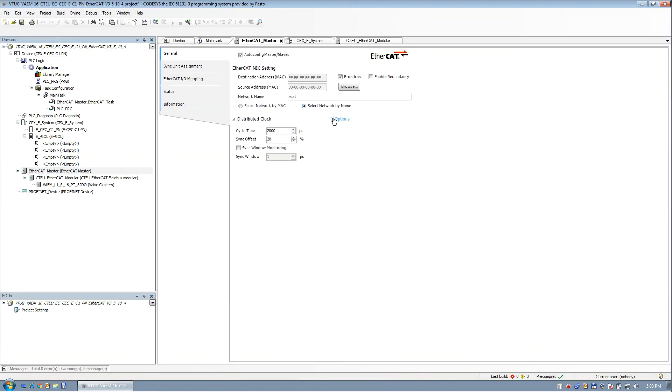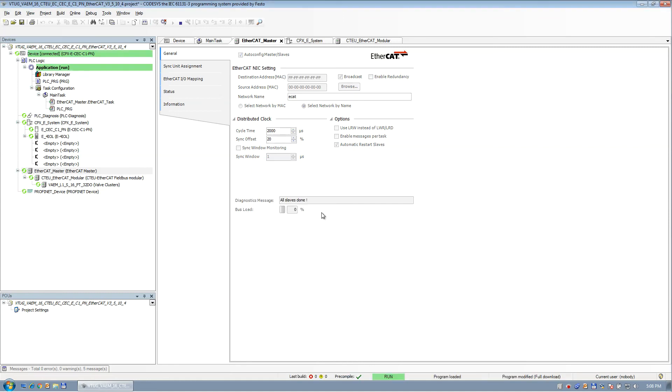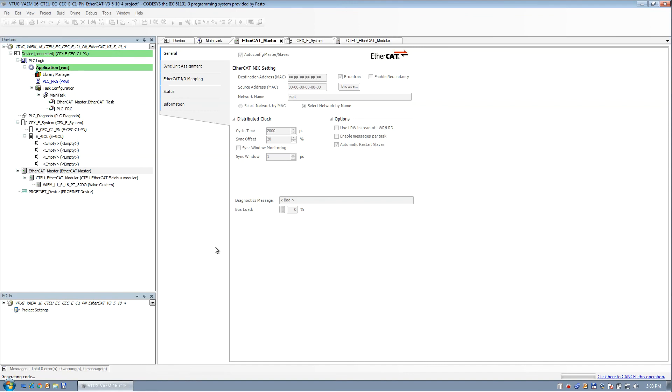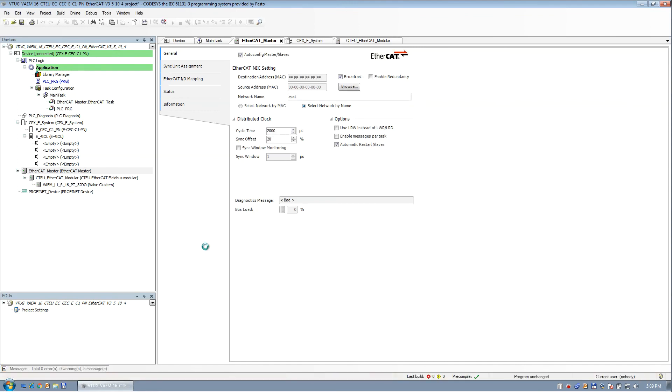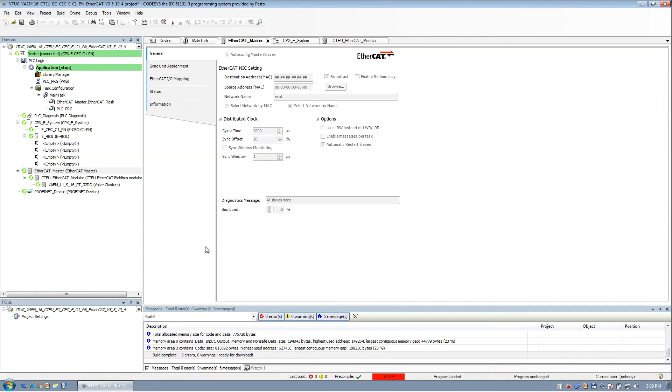So let's go back offline in a sec and look at the master. Because under options that are hidden, there's this little button here. Automatic restart. So I'm going to dump this back in. It's running. I'm going to pull the connector off. Bus goes down. I'm going to plug it back in. And the bus comes back up. Now, that's great. So there's another thing to learn.